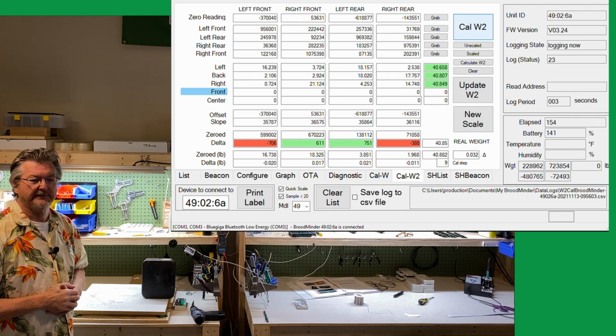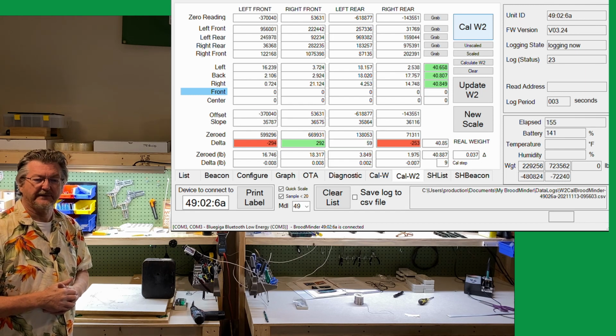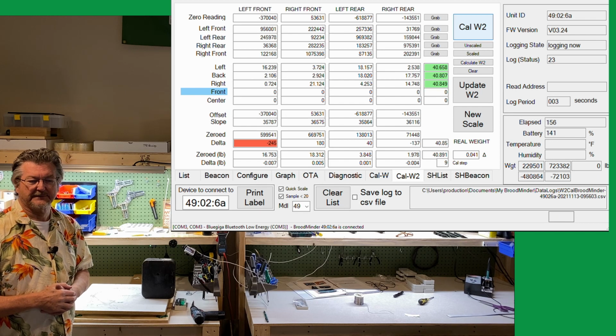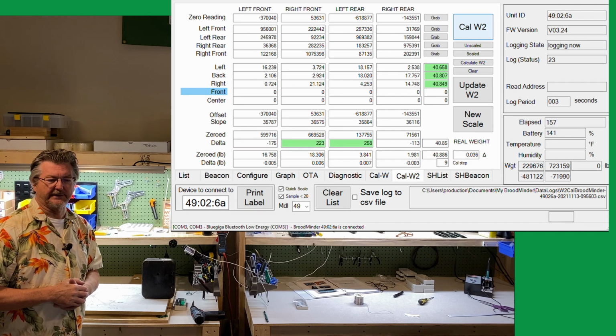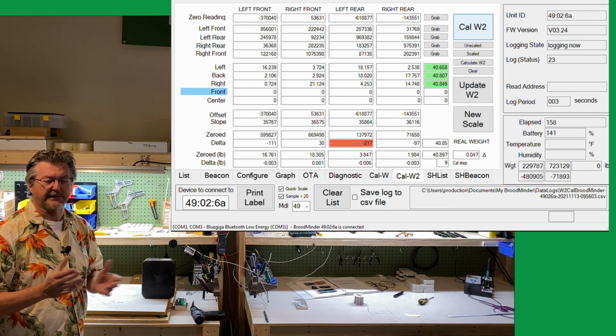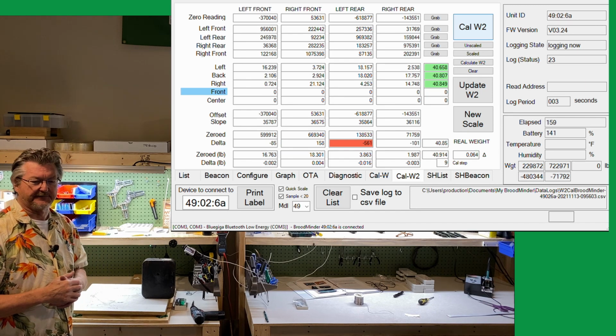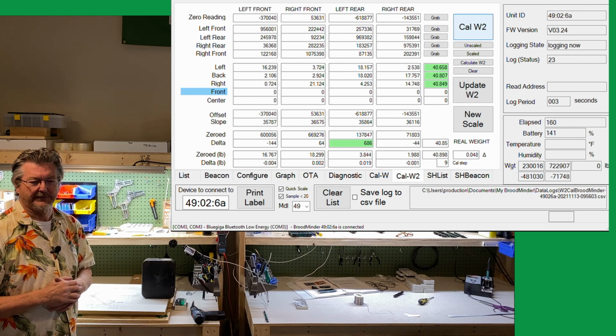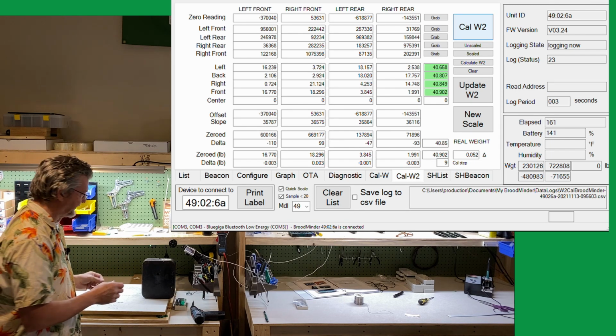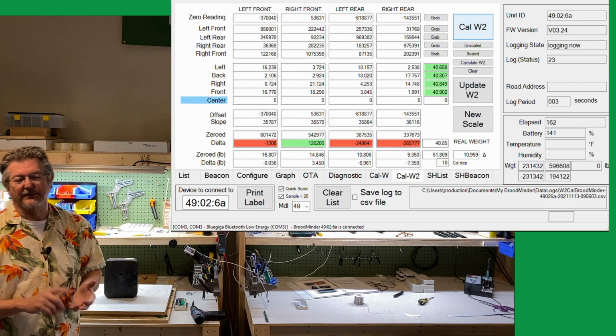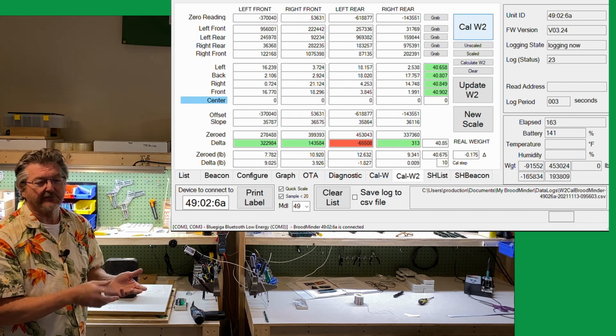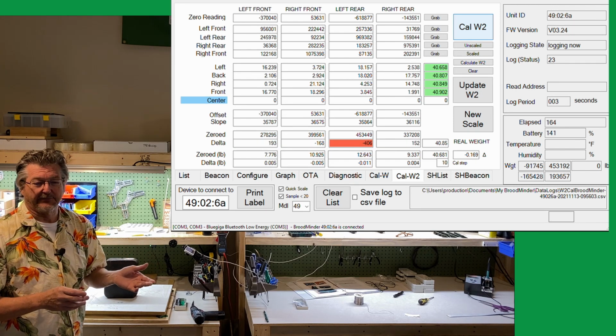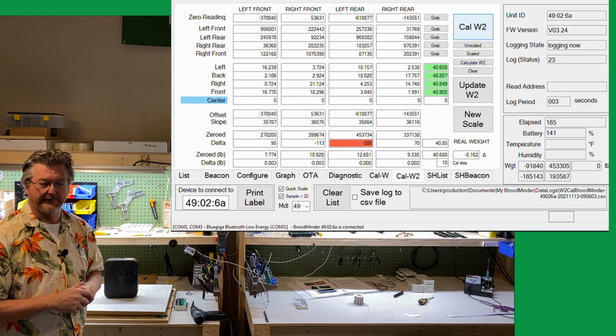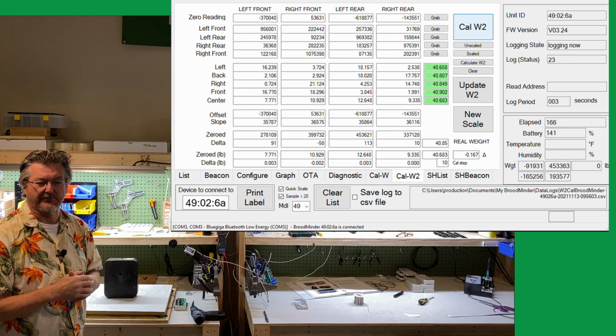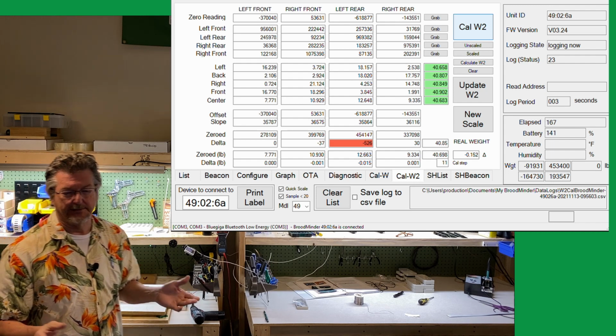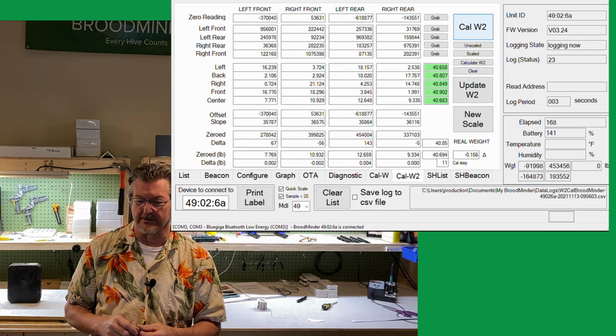Okay, it's looking good on all those. Now it's using the offset and slope values, which are also recorded in a file, so if something is wonky we can look at those and see what's happening. Usually what happens is some wires are reversed, so we fix that. Every once in a while we have a bad sensor, usually because we pulled on it too hard or something like that. Now we're all calibrated, and we've proven the values look decent.